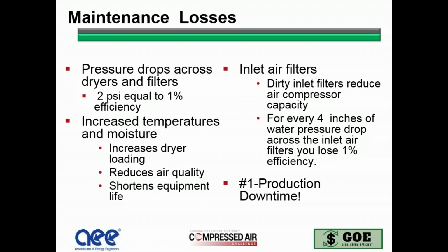Increased temperatures and moisture. So anytime you don't have the proper removal of heat in the system, and you don't have the capability, for example, of the intercoolers and aftercoolers of the compressor to get rid of that heat, it'll put hotter temperatures into our chiller dryers. And when you do that for a chiller dryer, every time you increase it, even from its design set point of 100, the 100s rule in the U.S., which is 100 PSI inlet, 100 CFM, and 100 ambient. So anytime you go off of those design parameters, you'll derate the dryer.